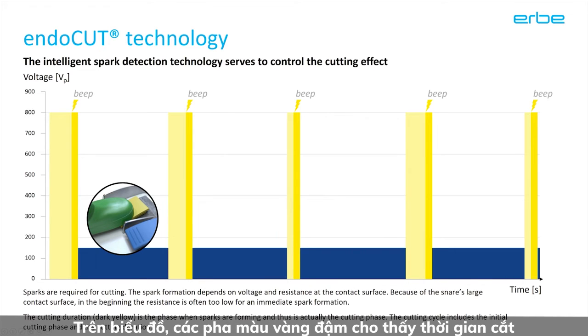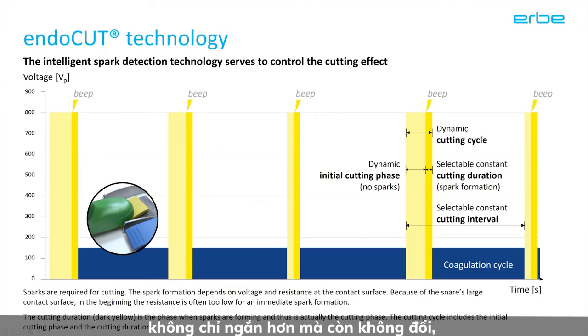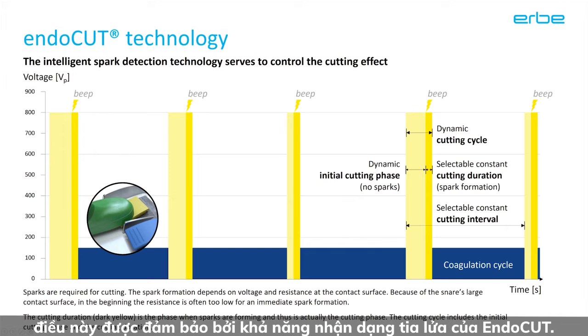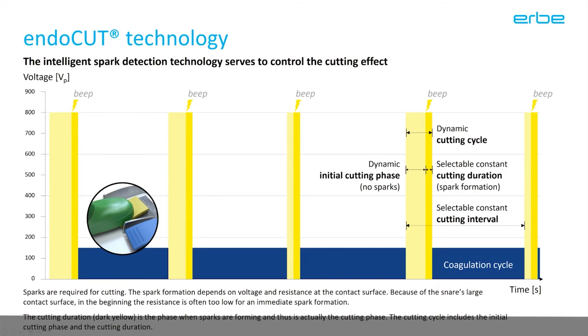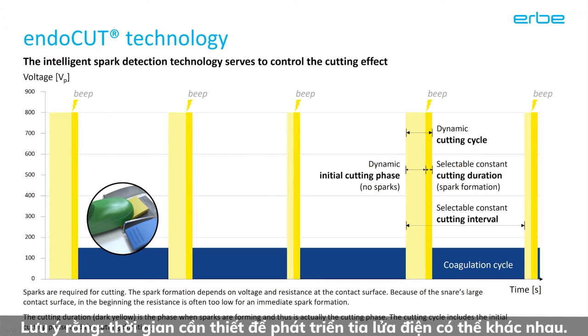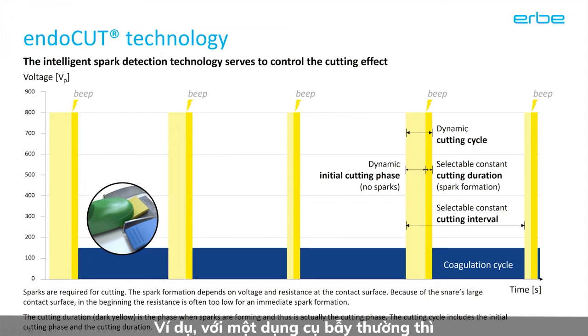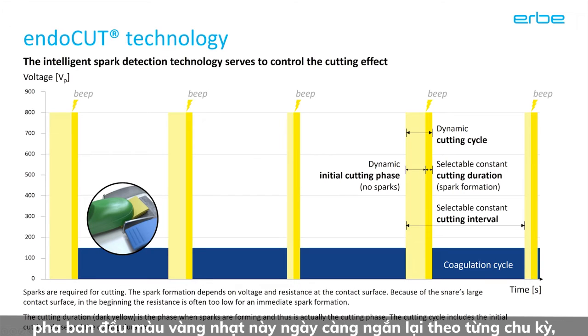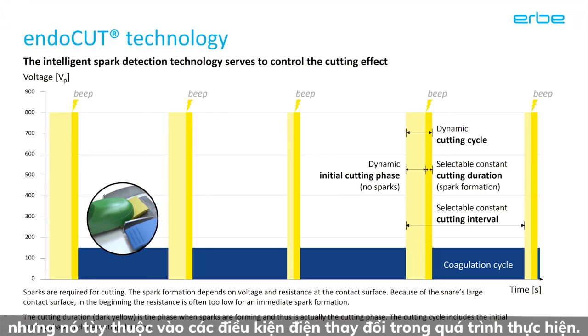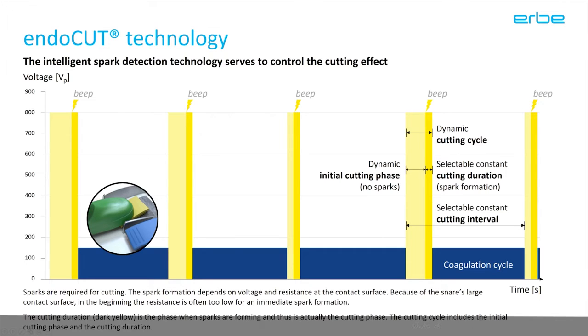As you see in the graph, the dark yellow cutting duration phases are not only shorter, but also constant. This is ensured by the EndoCut's spark recognition. You can set the cutting duration, the cutting interval, and the coagulation intensity individually, as I will show you later on. Note that the time it takes to develop the sparks can vary. With the example of a snare instrument, typically this light yellow initial phase becomes shorter and shorter with each cycle, but depending on the changing electrical conditions during the procedure, sometimes it may also become a bit longer again.